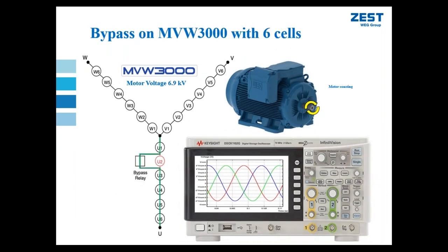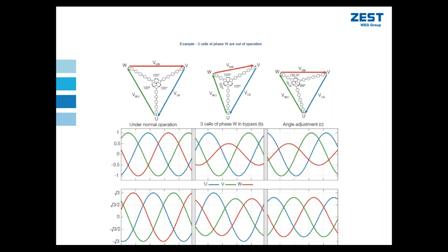This makes a lot of sense when you start increasing the number of power cells in each phase, because now the percentage of voltage loss if you lose one power cell becomes very small and almost negligible in many cases. That's one method of bypass.